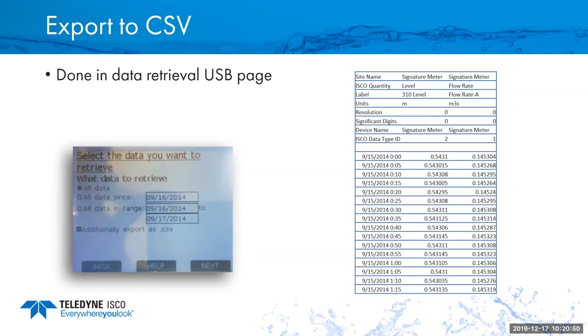You could retrieve it with a USB stick. All you do is walk up to the unit and plug a USB drive into the signature flow meter. The signature flow meter will pop up a screen that allows you to retrieve data via CSV. Or there's the ability to download the data the same way with what we call text reports. Those text reports can be set up as a daily text report to give you min, max, average, total flow rate, or pH, or level, or whatever parameter you want to put in there. You can also set up a second one for, say, monthly. Those are all settable to whatever parameters you're looking to get.